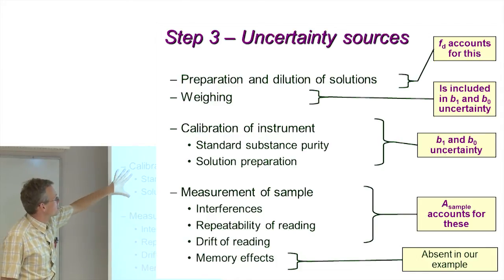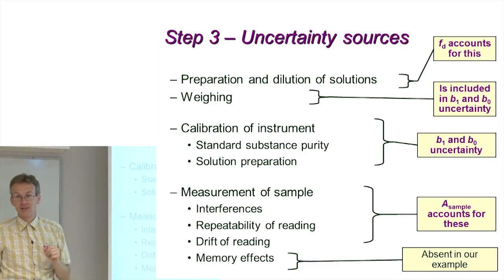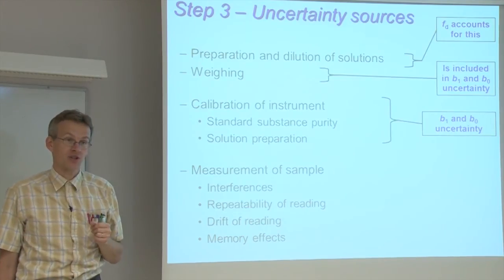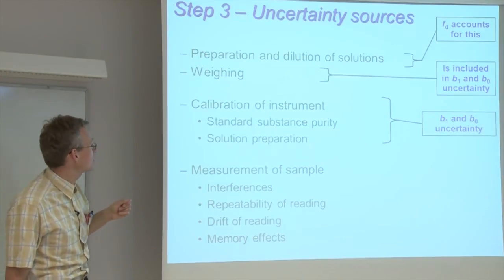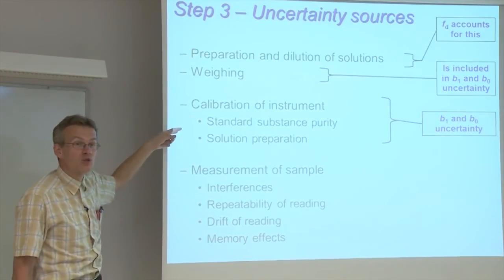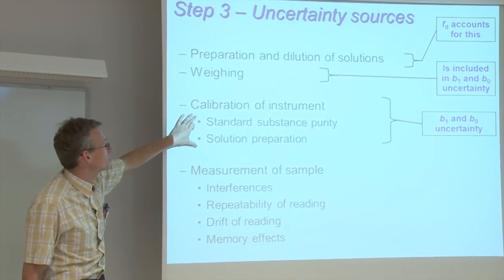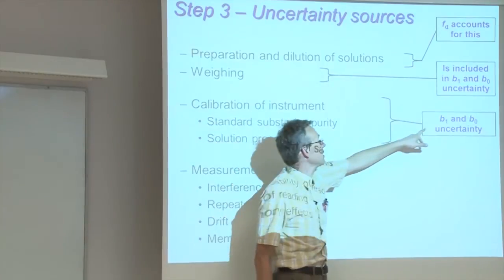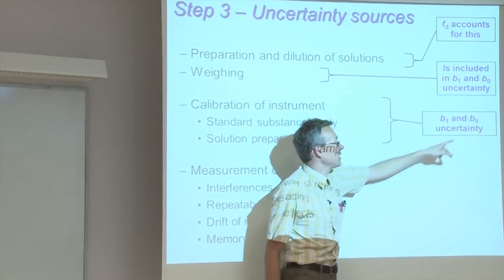Then comes calibration of the photometer, which has two uncertainty sources: the purity of the standard substance, and also the preparation of solutions. Both of these uncertainty sources have an effect on the calibration graph slope and the intercept, represented by B1 and B0.